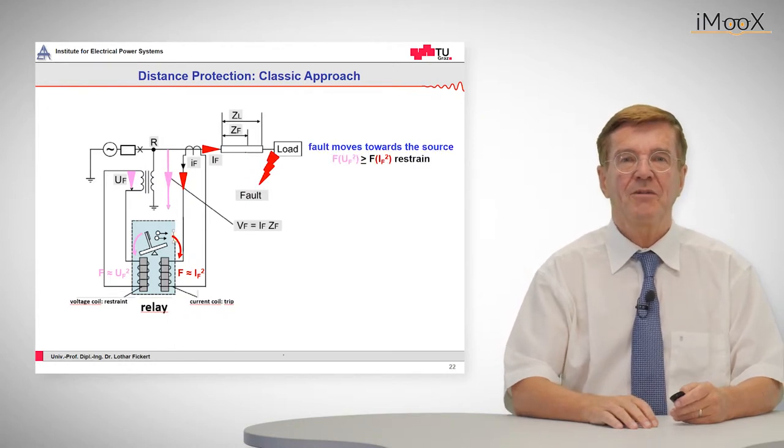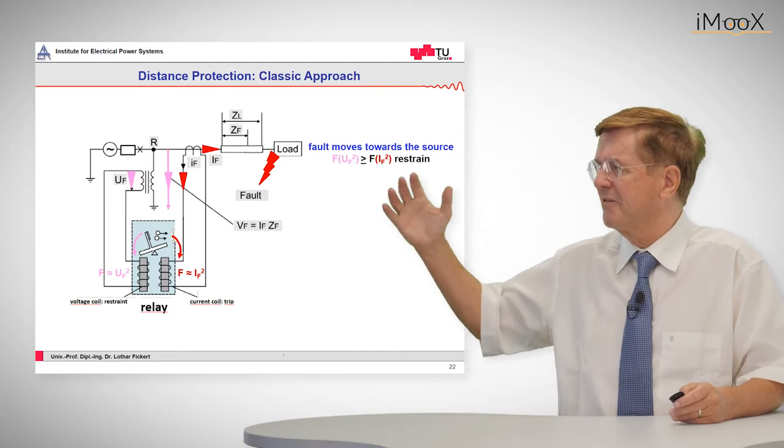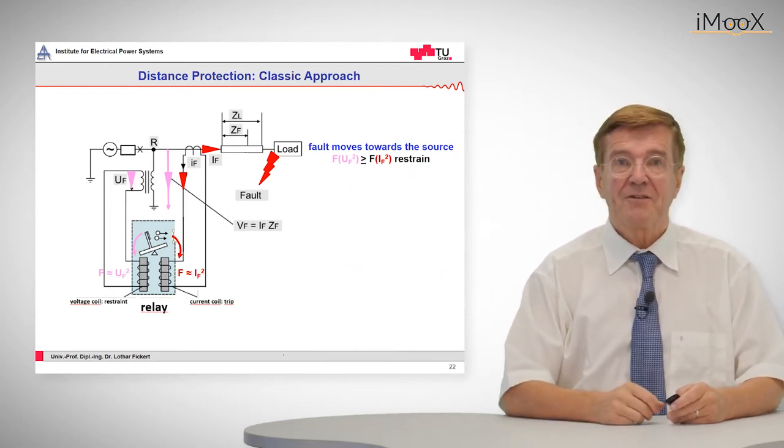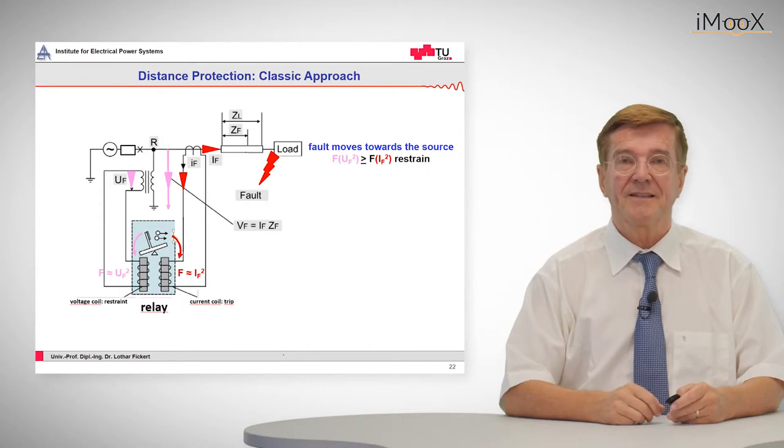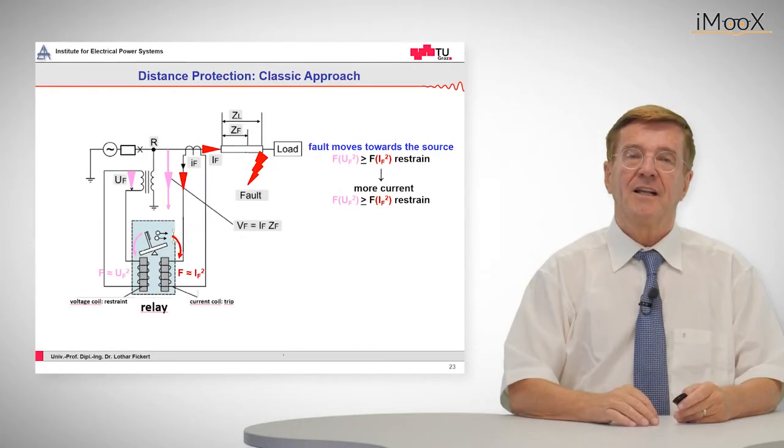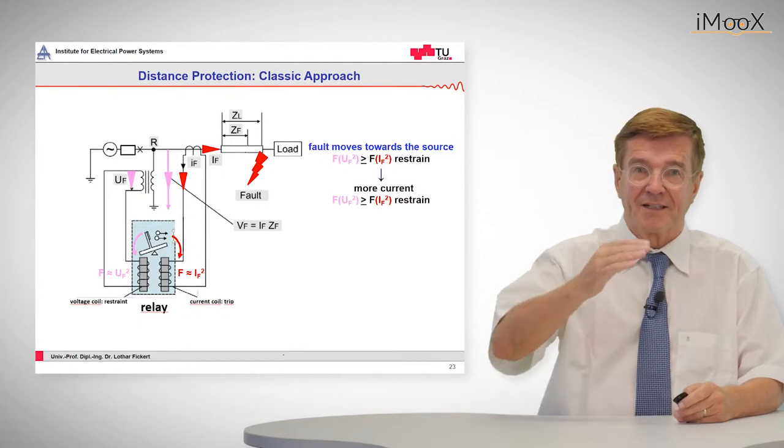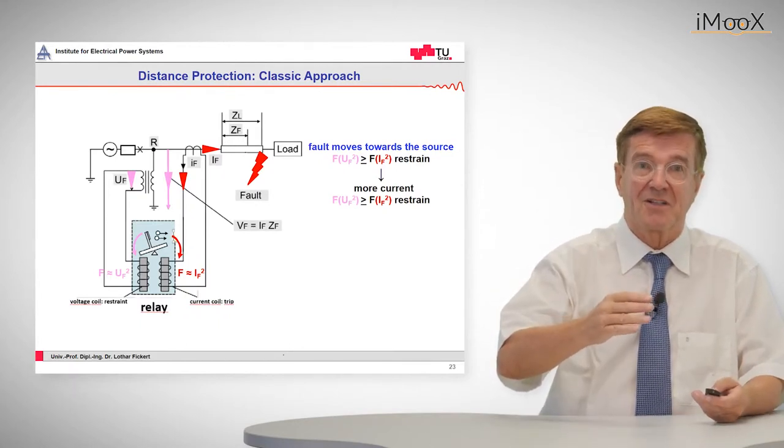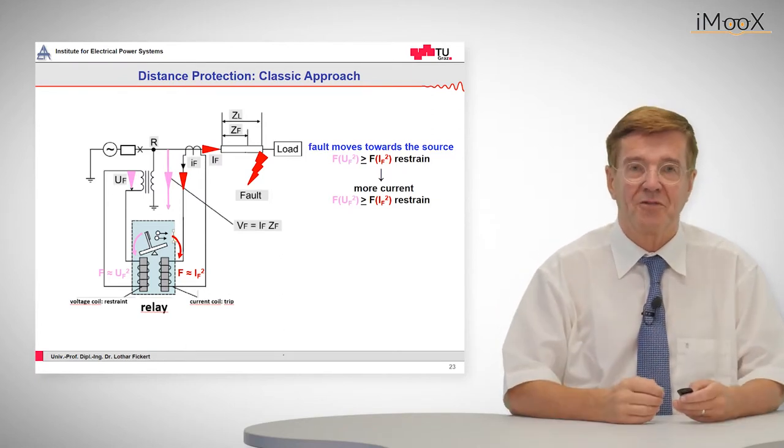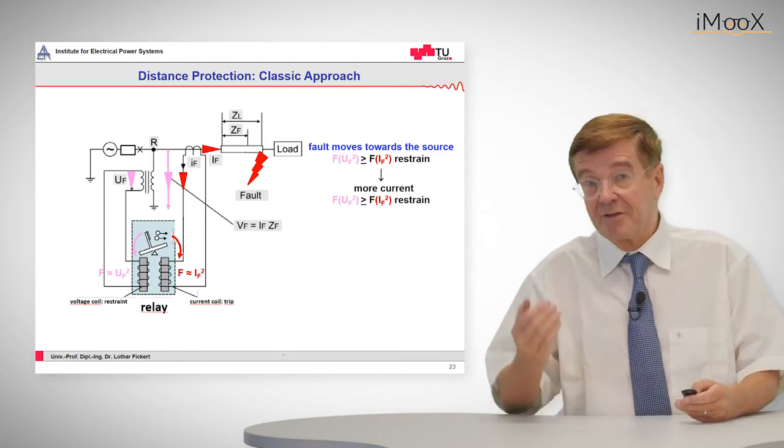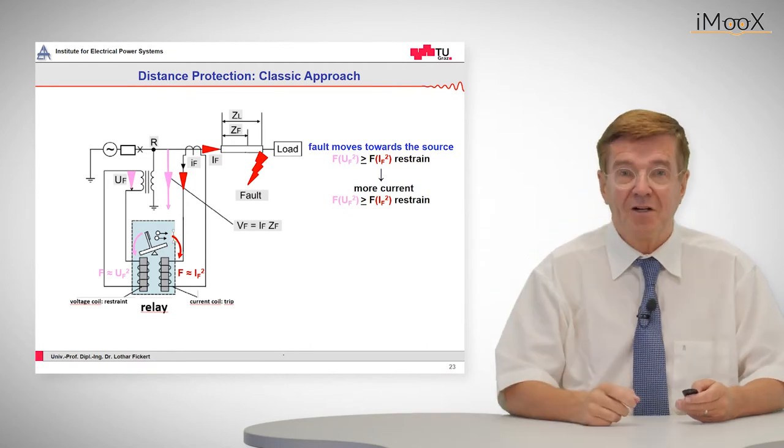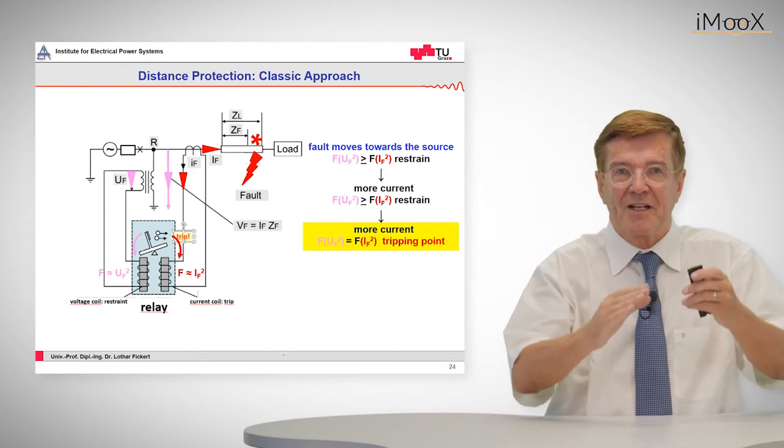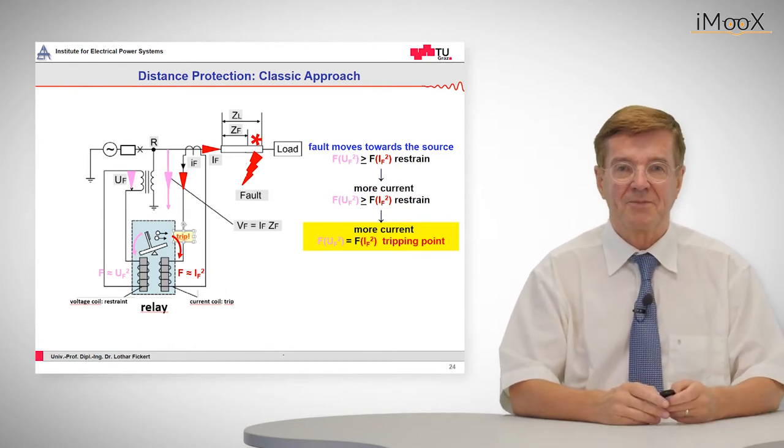Now if we have a fault or a high impedance at the far end or behind this line the restrained forces are higher than the trip forces, the current forces. If we move further in one side comes down which is the restraint force, the voltage source, because the closer we get to the relay the less residual voltage is monitored there. And on the other hand the current will go up and that goes on till we at a certain point have an equilibrium and behind this we have a trip zone.